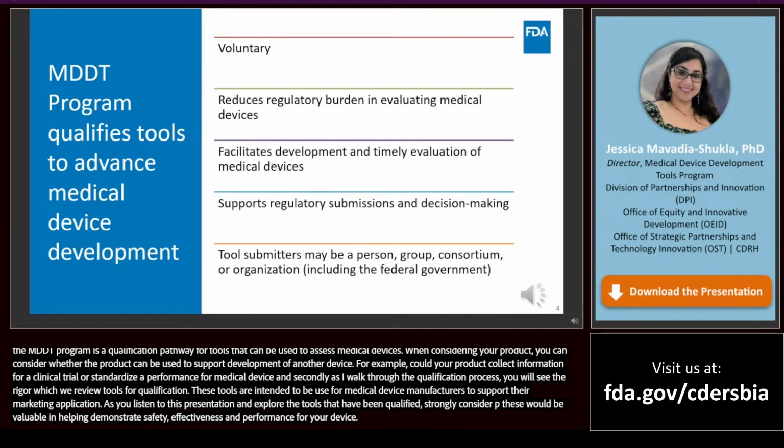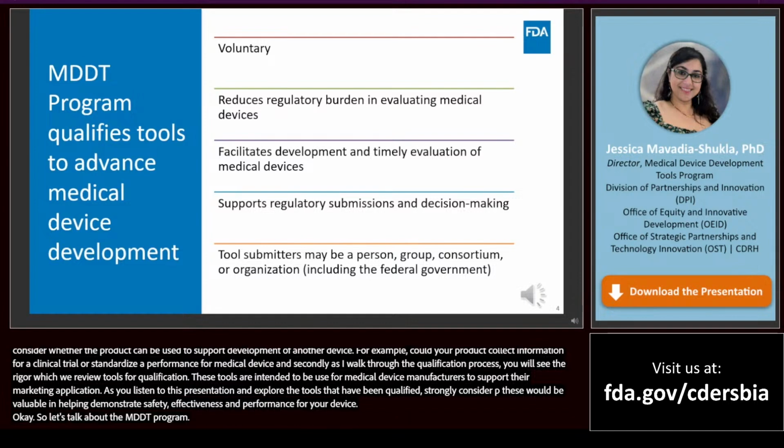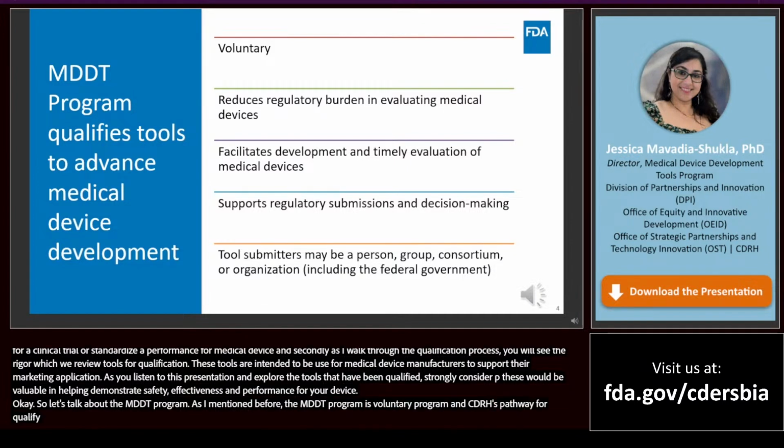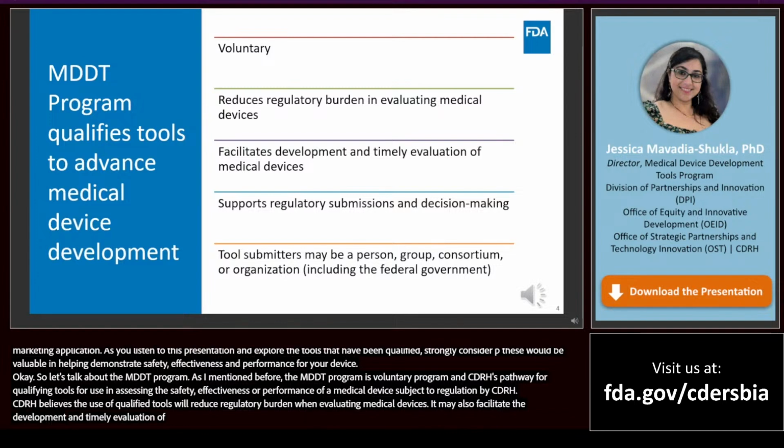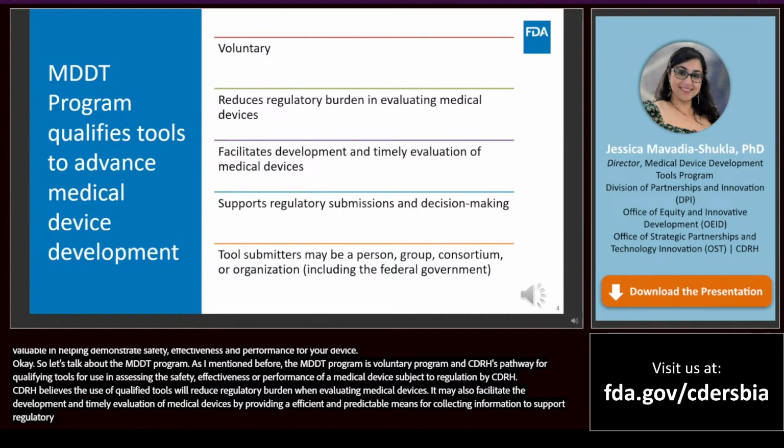Okay, so let's talk about the MDDT program. As I mentioned before, the Medical Device Development Tools program is a voluntary program and CDRH's pathway for qualifying tools for use in assessing the safety, effectiveness, or performance of a medical device subject to regulation by CDRH. CDRH believes the use of qualified tools will reduce regulatory burden when evaluating medical devices. It may also facilitate the development and timely evaluation of medical devices by providing a more efficient and predictable means for collecting the necessary information to support regulatory submissions and associated decision-making.